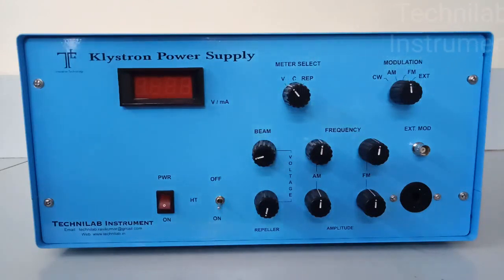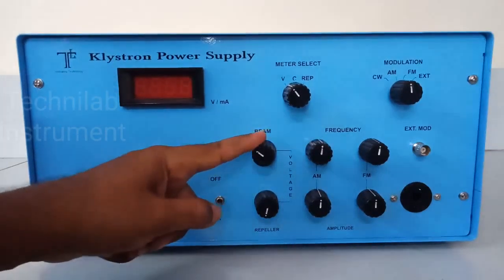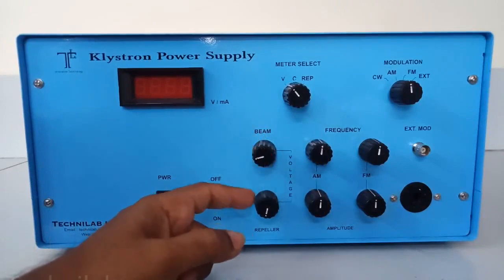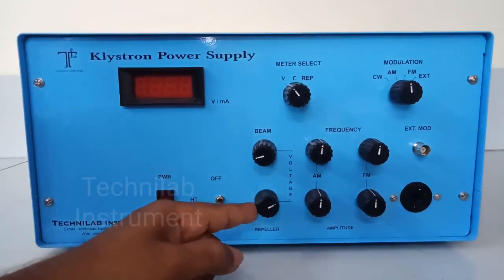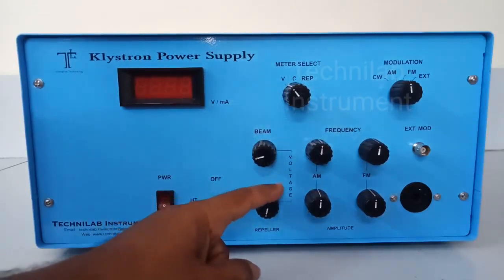This is your Klystron power supply. Before turning on this power supply, we have to follow some precautions for safety. This is the beam knob — keep it at the minimum position, meaning fully rotated anti-clockwise. And this is the repeller knob — this should be at the maximum position, meaning fully rotated clockwise.